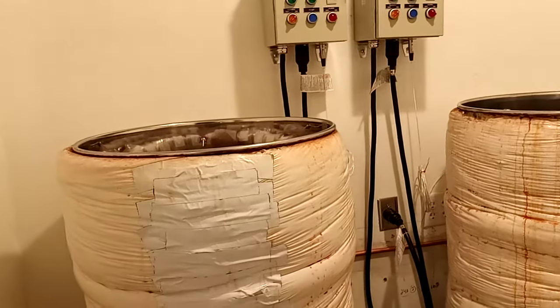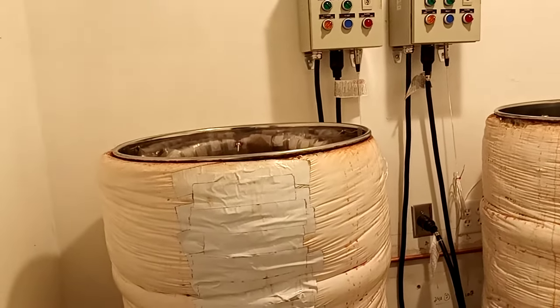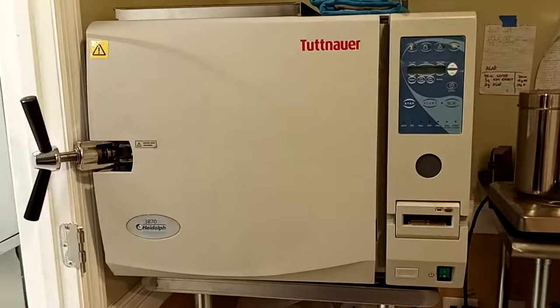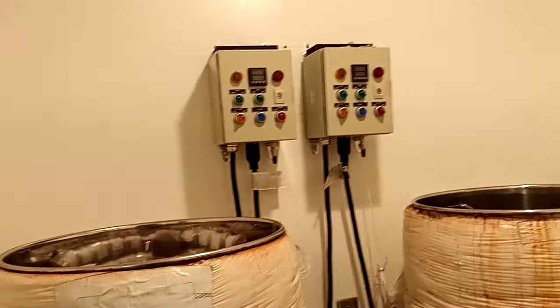Most of our sterilization is done through the atmospheric steam sterilizers, although we do use our autoclave — our Tuttnauer — for instrumentation and for liquid culture. So we don't do liquid culture or instruments in these sterilizers.